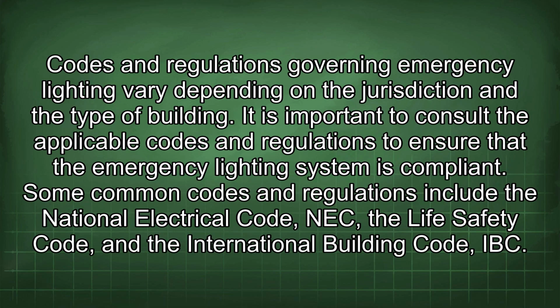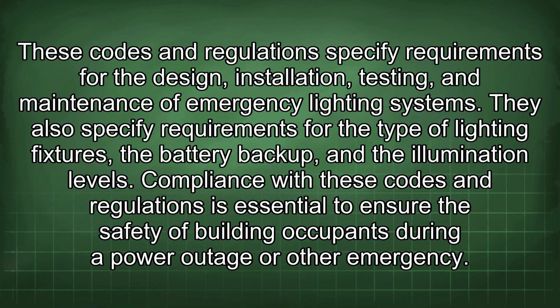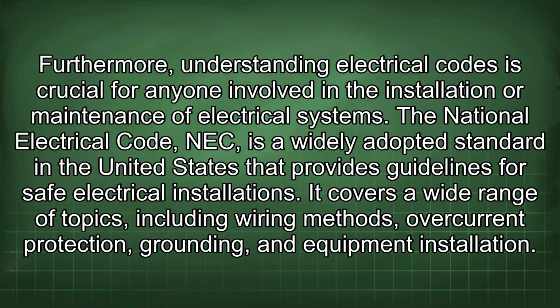Codes and regulations governing emergency lighting vary depending on the jurisdiction and the type of building. It is important to consult the applicable codes and regulations to ensure that the emergency lighting system is compliant. Some common codes and regulations include the National Electrical Code, NEC, the Life Safety Code, and the International Building Code, IBC. These codes and regulations specify requirements for the design, installation, testing, and maintenance of emergency lighting systems. They also specify requirements for the type of lighting fixtures, the battery backup, and the illumination levels. Compliance with these codes and regulations is essential to ensure the safety of building occupants during a power outage or other emergency.